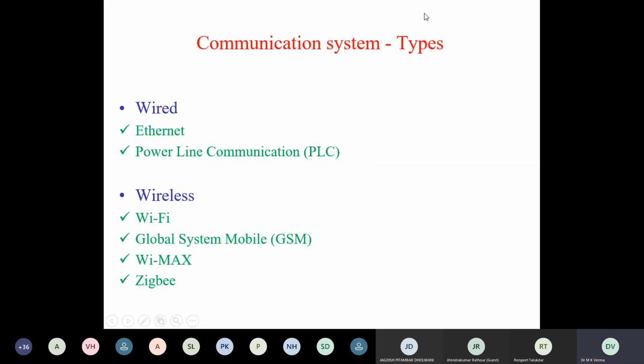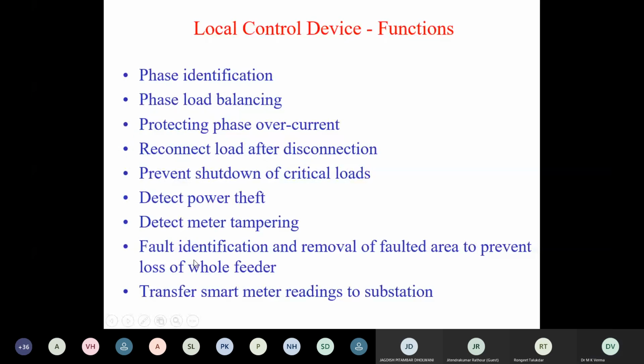The communication system may be either wired, through Ethernet and power line communication (PLC), or wireless, such as Wi-Fi, GSM (Global System for Mobile), WiMAX, Zigbee, etc. Then, there may be a local controller put at the DT, distribution transformer, and a master controller may be put at the main substation.